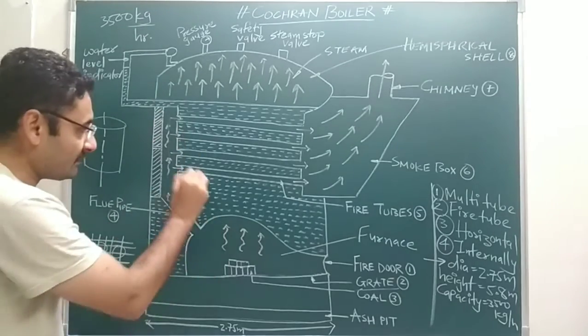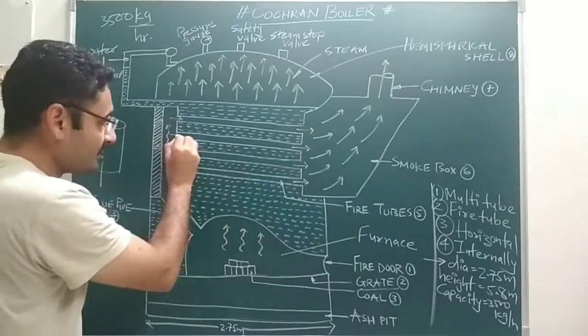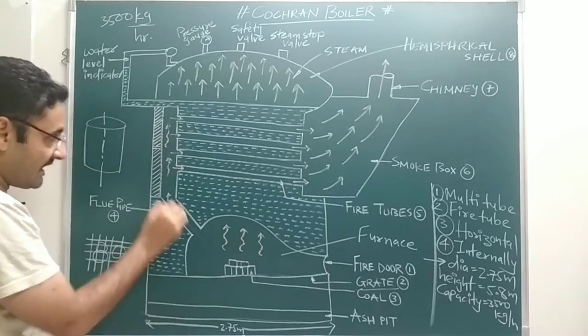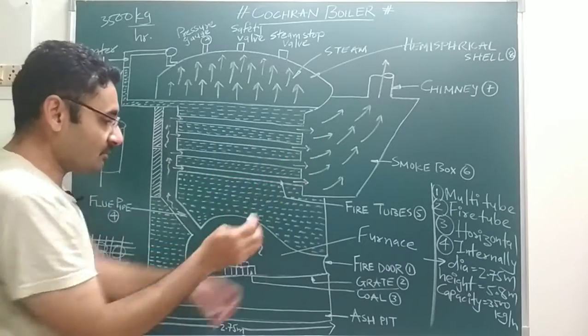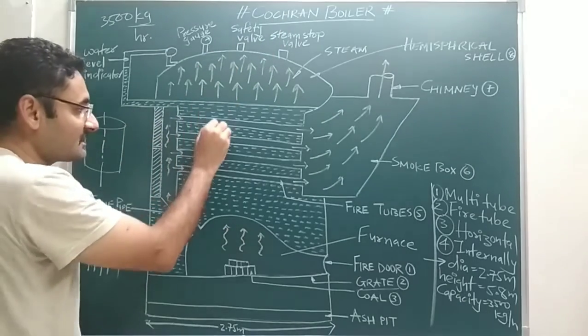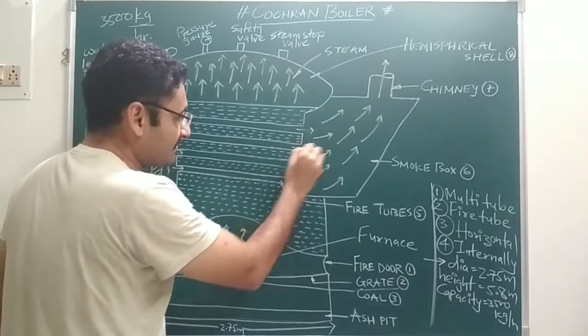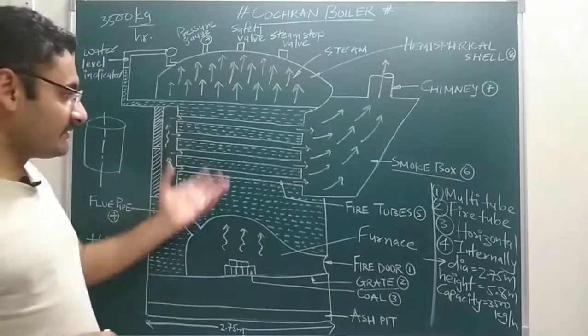Due to the combustion of coal, hot flue gases are produced. Those hot flue gases travel through the flue pipe, which is connected to the fire tubes. The fire tubes are surrounded by water, and inside the tubes, the hot flue gases are present. The flue gases enter the fire tubes, which are surrounded by water, and the flue gases reject heat to the water, converting it into hot water. The flue gases then pass through the smoke box, which is connected to the chimney, and are released into the atmosphere.